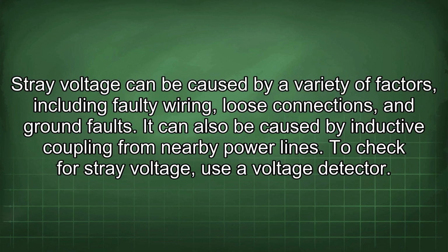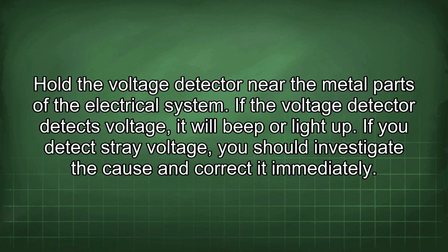Stray voltage can be caused by a variety of factors, including faulty wiring, loose connections, and ground faults. It can also be caused by inductive coupling from nearby power lines. To check for stray voltage, use a voltage detector. Hold the voltage detector near the metal parts of the electrical system. If the voltage detector detects voltage, it will beep or light up.